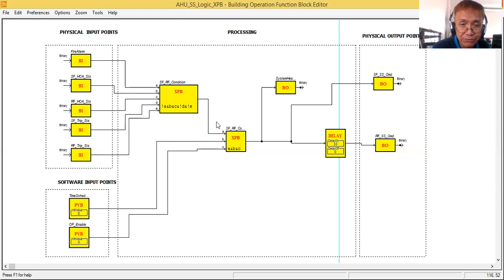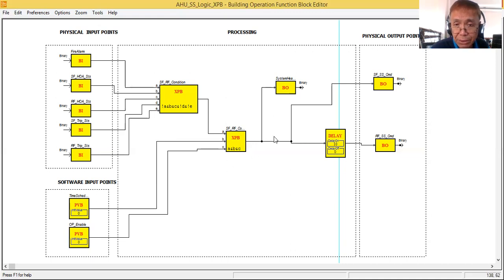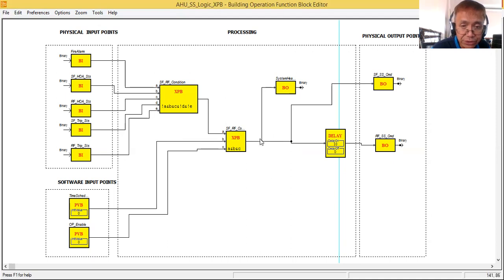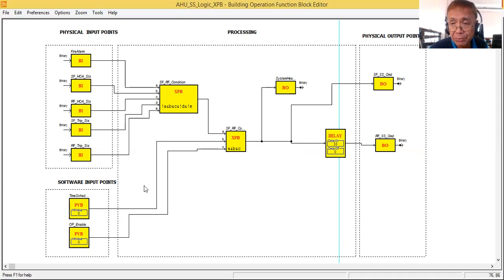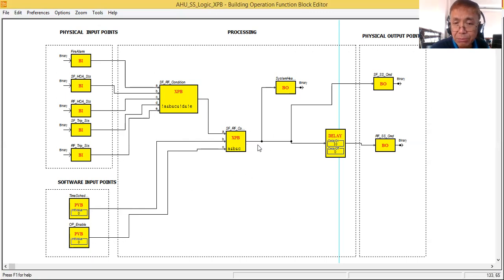If that is true, I use the output of this block as one input to a second expression block, which has three inputs. The expression for the second block is: A AND B AND C — all conditions must be true before it gives a binary output of one. The other inputs are software input points from the BMS graphics: time schedule and operator enable.